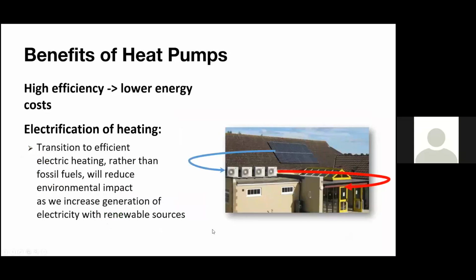So moving on here, looking at the benefits of heat pumps. Again, we touch on the efficiencies a little bit later, but looking at the 10,000 foot level in cooling, these air source heat pumps tend to use inverter compressors, variable speed compressors. So they tend to be better machines, more efficient than your usual square cube air conditioner outside, or even your regular package rooftop unit. Generally in cooling in the summer, you're not using the heat pump function. You're cooling, but you'll do it much more efficiently. You should be able to use less power, and you should have an advantage there in the summer in cooling.